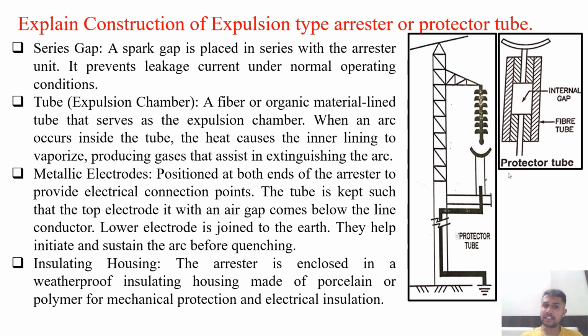It prevents leakage current under normal operating conditions. A tube or expulsion chamber like this. The tube is a fiber or organic material lined tube that serves as the expulsion chamber. When an arc occurs inside the tube, the heat causes the inner lining to vaporize, producing gases that assist in extinguishing the arc.